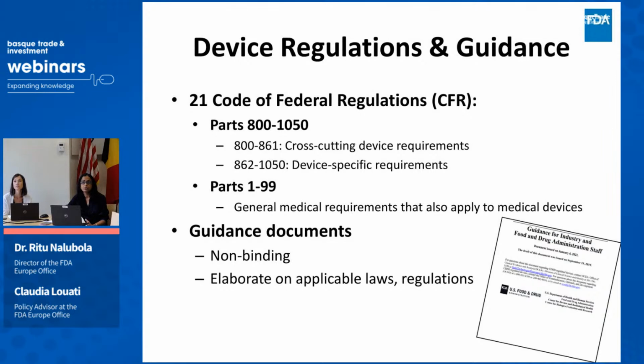In addition to regulations, we also have guidance documents. So FDA issues guidance documents mainly to help industry to comply with the regulatory requirements. Whereas regulations are requirements, meaning you must abide by those and comply with those, the guidance documents are more elaborative. They explain what the regulation is and they give you some guidance on how to comply with those requirements. So guidance documents from that standpoint are non-binding, and they elaborate on specific laws and regulations that apply to a specific product or an issue. For medical devices, as well as for other products, we have several guidance documents that we've issued for industry, and all of those are posted on our webpage.